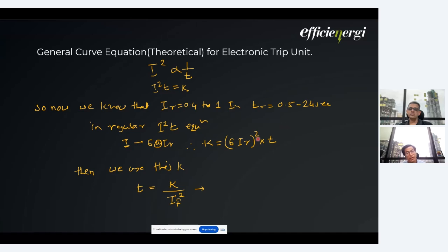That is, when the fault current goes to 6 times the IR. Once this K is calculated, we can have the operating time for each and every fault current for which we want to know the operating time. So this K is fixed, and we can have different operating fault currents, let's say 2 times, 3 times, and we can calculate this T. Again, this T is a theoretical value, and again, this will have tolerances added to it.